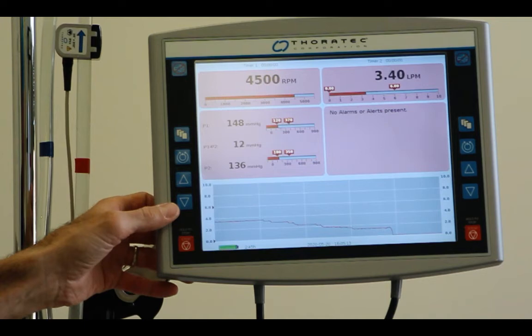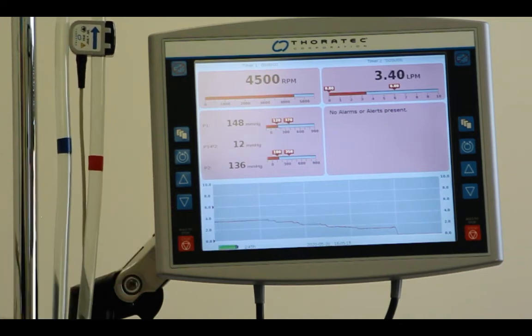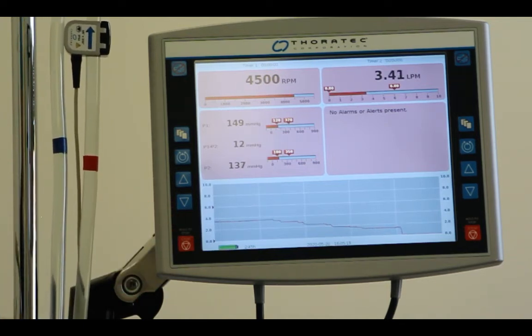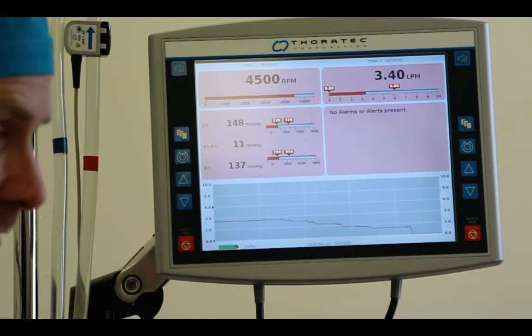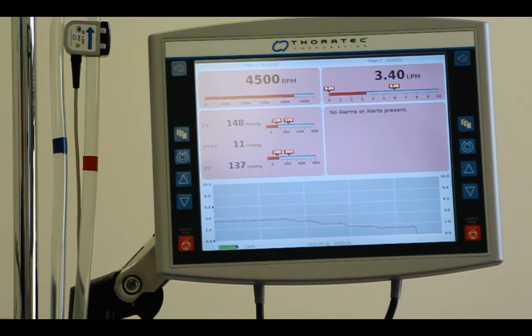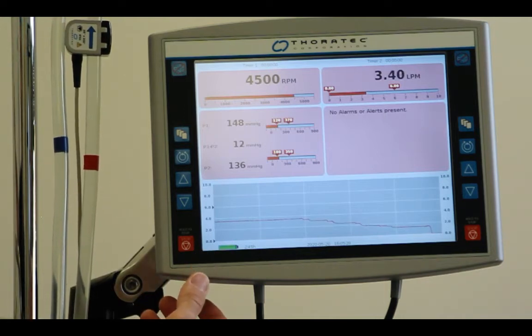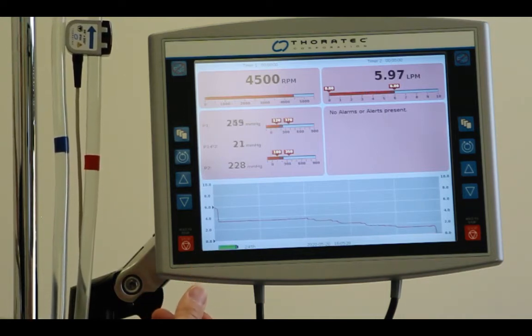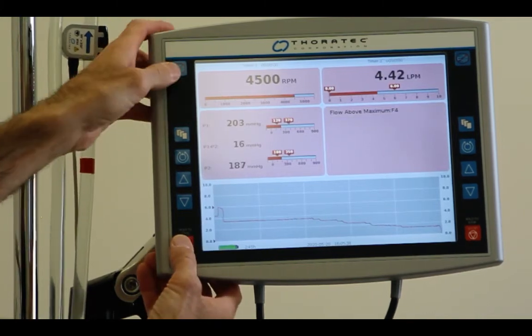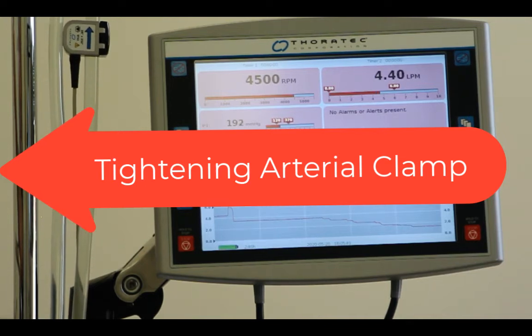Doctor, are you happy with the position of that venous cannula? Also, of course, before you do that, you look around for any kinks on your side. You've got bad data. It's either your fault or it's their fault. Make sure it's not your fault before you start asking them to fix their things. So let's redo this now with an afterload problem. So I'm going to back that clamp off for you so that it's not a problem. And I'm going to tighten this arterial clamp. And we're going to turn this pump off.